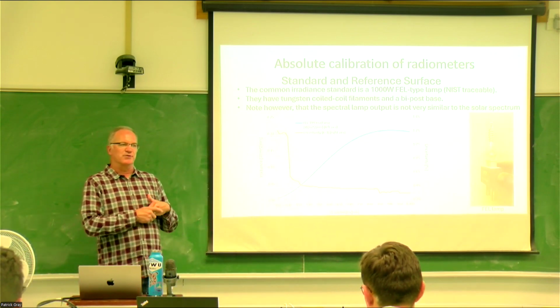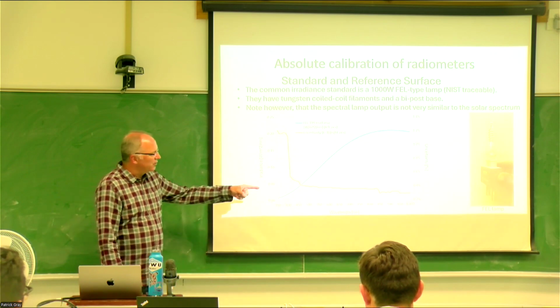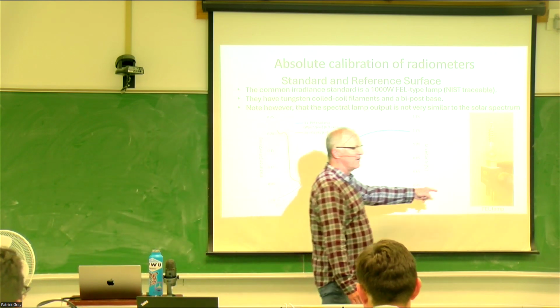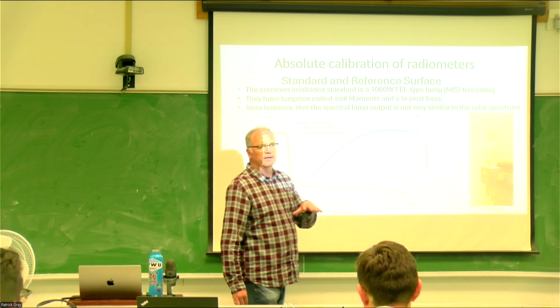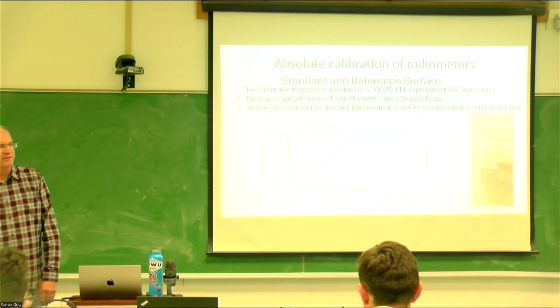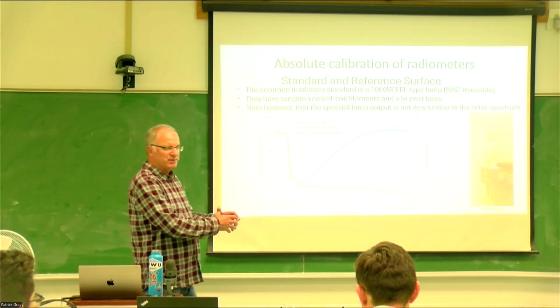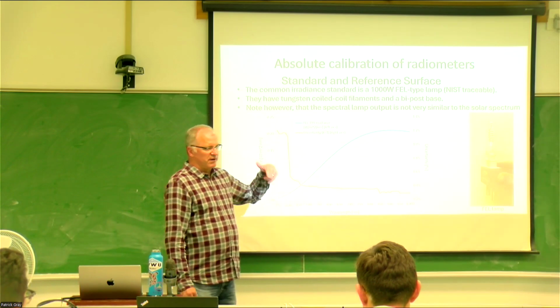That's how you get to actual pure calibration. So this is what's called a transfer function. There are different ways that NIST, the National Institute of Standards and Technology, has to do the cryogenic calibration that really sets the standards for the measurement itself. But this is a transfer function.